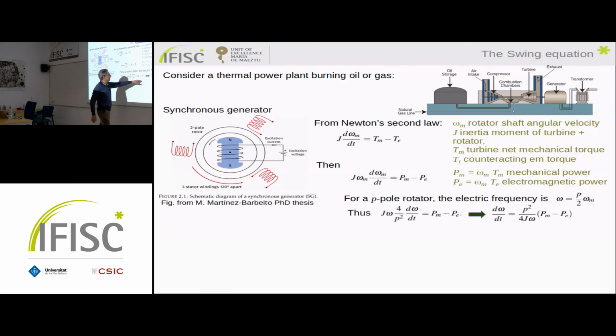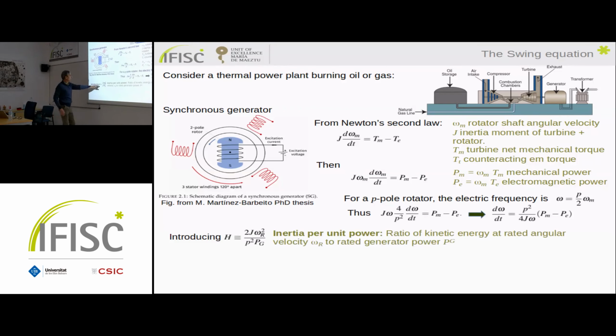Now you substitute this in, and you get this equation. You introduce a coefficient which engineers call the inertia per unit power - basically the ratio between the kinetic energy at the rated angular frequency of 50 Hertz and the generator power, which I'll call PG. This is a generator with a rated power of 100 megawatts. So they introduce this unit, H, and then you get this equation.